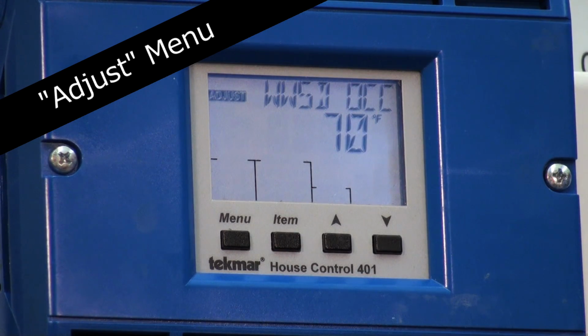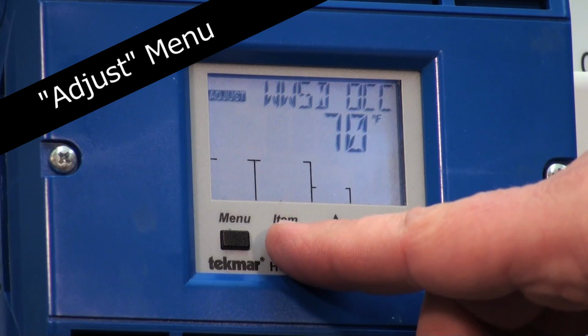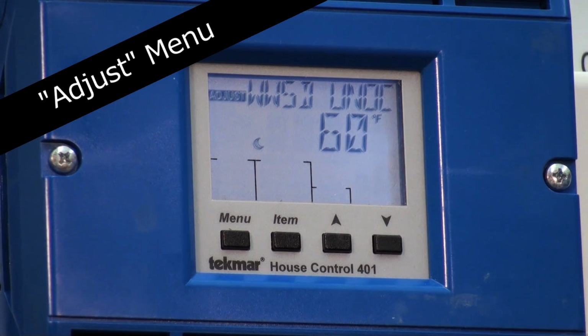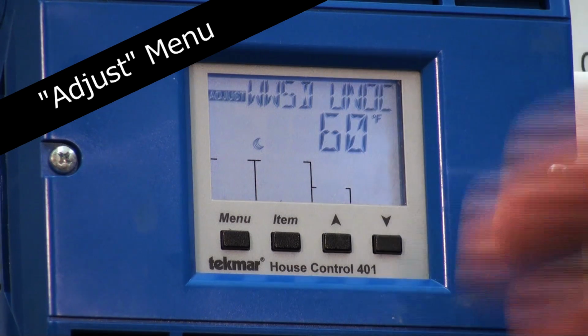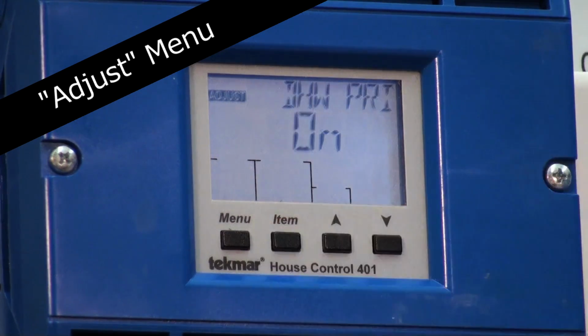Warm weather shutdown in the occupied mode. This is during the day, it gets above 70 degrees outside, the heating system will be shut off. No matter what you do with the thermostats, the entire system will go into a warm weather shutdown. You also have a warm weather shutdown unoccupied. So if it's 60 degrees outside in an unoccupied mode, we'll also shut the system down.